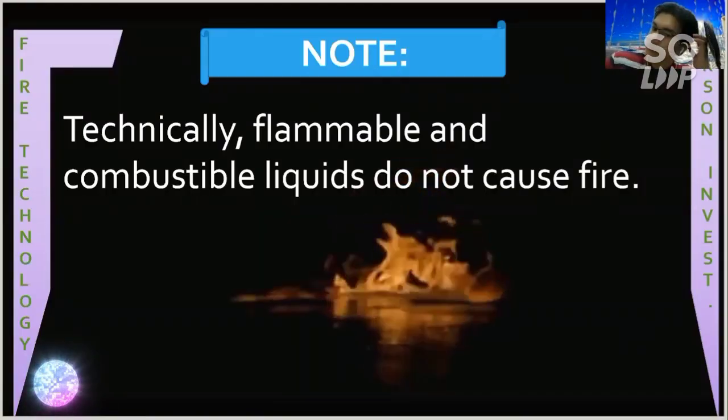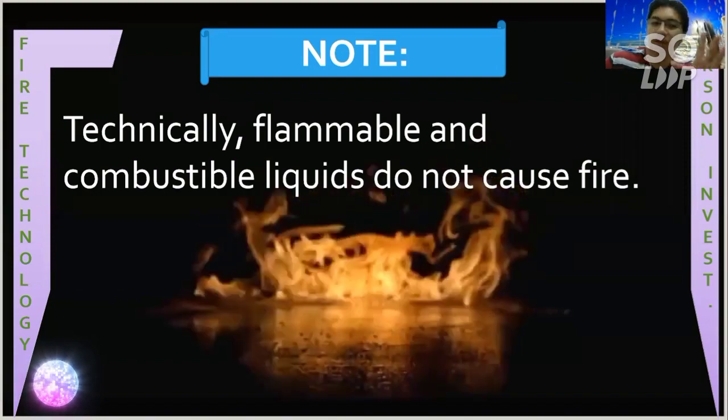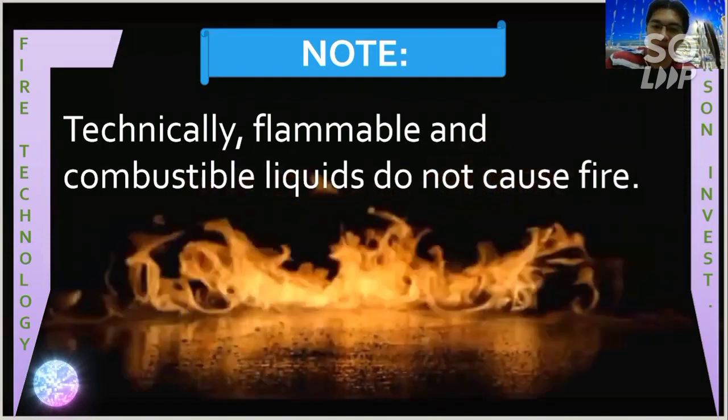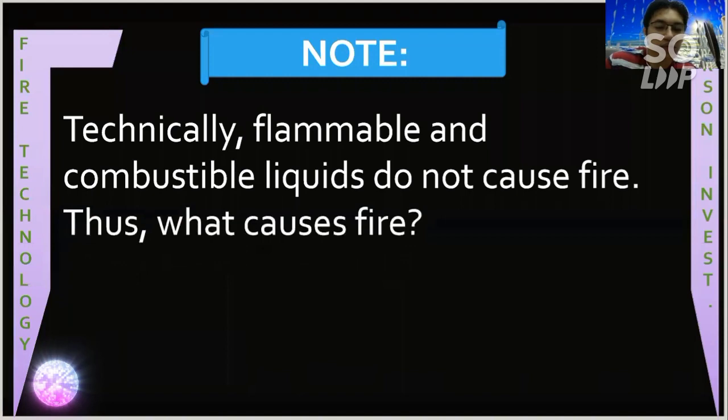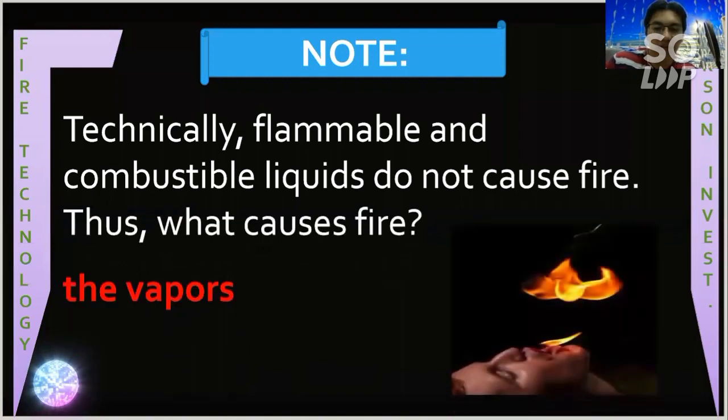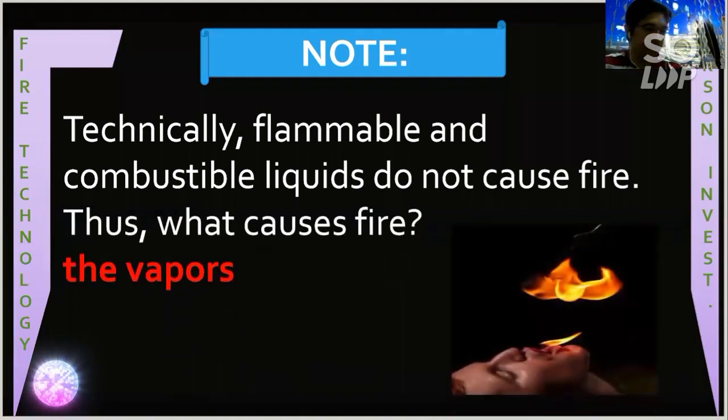So, yung sinabi natin, technically, flammable and combustible liquids do not cause fire. What causes fire? It is the vapors. It is the vapors. They produce vapors, which burn or explode when exposed to air under the influence of heat.